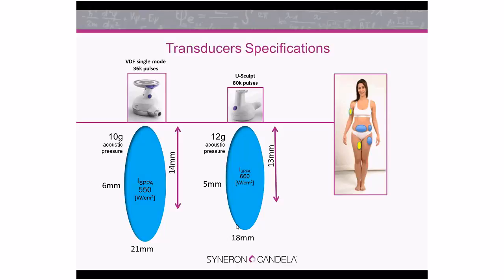The U-sculpt energy is higher than the VDF, only in UltraShape power. So we took the energy up 20% to 12 grams acoustic pressure, okay? And you can see that the dimension of the focal volume of the VDF transducer is bigger than the dimension of the focal volume of the U-sculpt transducer. And this is why, in order to cover the same area size, we need more pulses with the U-sculpt than with the VDF.